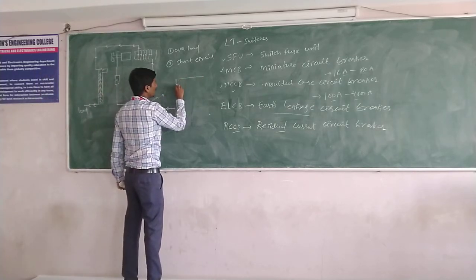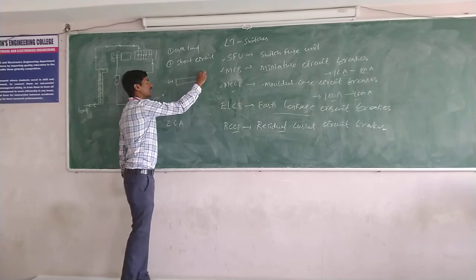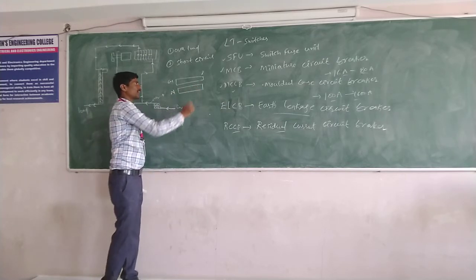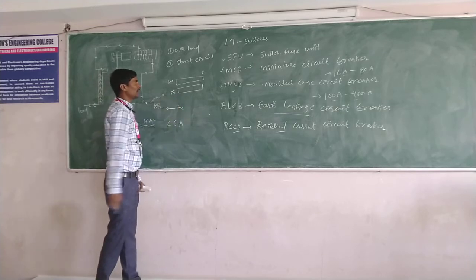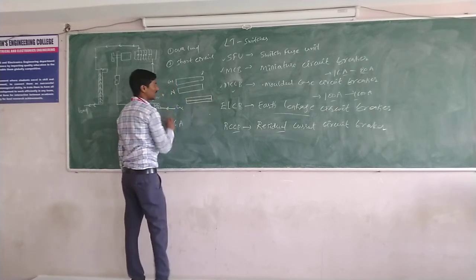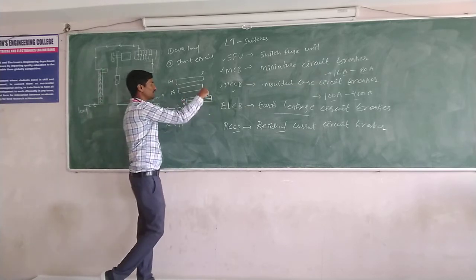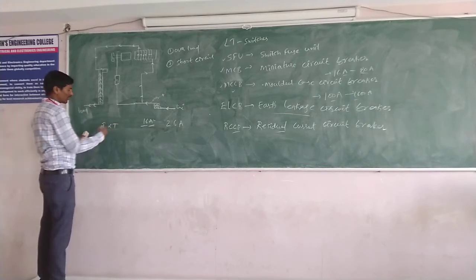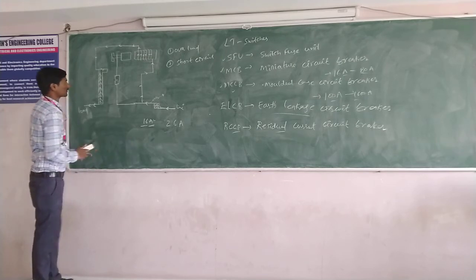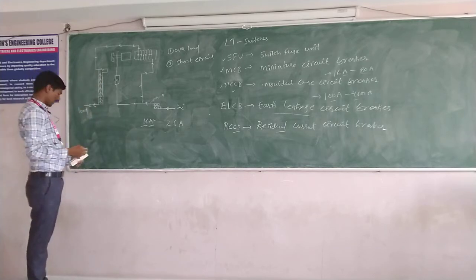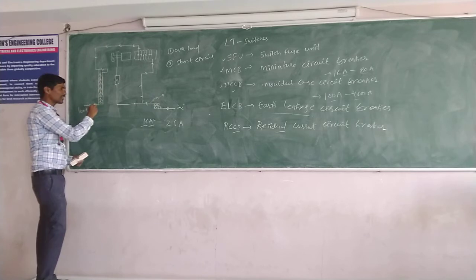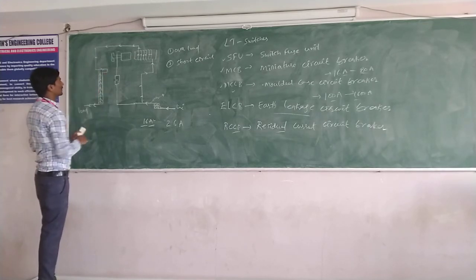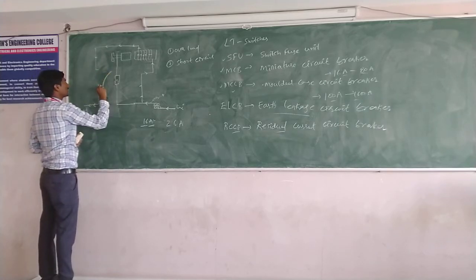The current also flows through the bimetallic strip. The function of the bimetallic strip is: if you take a single material and heat it, it will bend in one direction. But if you take two different materials — like copper and aluminum — and combine them, whenever you apply heat, one material expands more than the other, so it bends in one particular direction. We know that current is proportional to temperature, so whenever overload current flows through the bimetallic strip, it heats up and bends.